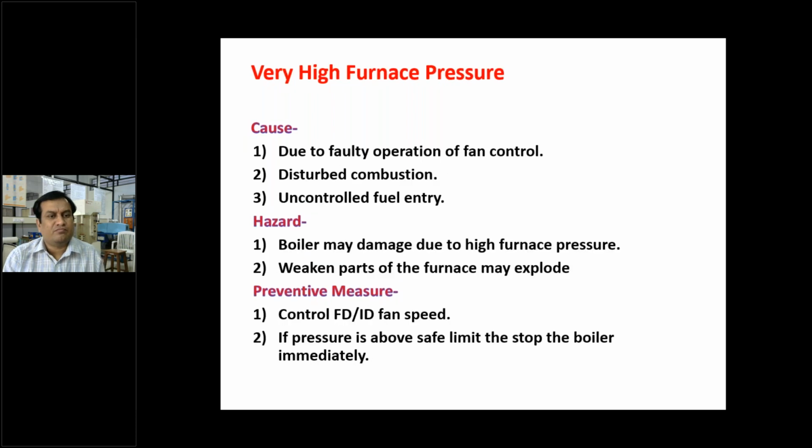Then the next problem may be very high furnace pressure. What is the reason for this pressure increase? Faulty operation of fan control, disturbed combustion, and uncontrolled fuel entry. These are the different causes due to which very high furnace pressure may be created in the furnace. What is the hazard due to this high pressure? The boiler may be damaged due to high furnace pressure, and weakened parts of the furnace may explode.